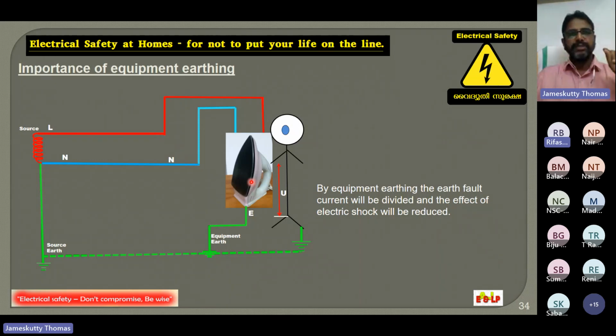Suppose we do not have such a protection device, we can get protection up to a limit, since the earthing and human body paths are in parallel, and thus the fault current that may pass through the human body will be lesser in quantity. See here, this human body path and this earth path will be in parallel, and if there is a fault current, we have a lesser chance of getting electrocuted because current is passing through this earth. So up to a limit we will be getting protection. But remember, RCCB along with earthing will always give 100% protection in such a case. I will explain the function of RCCB in a later slide.